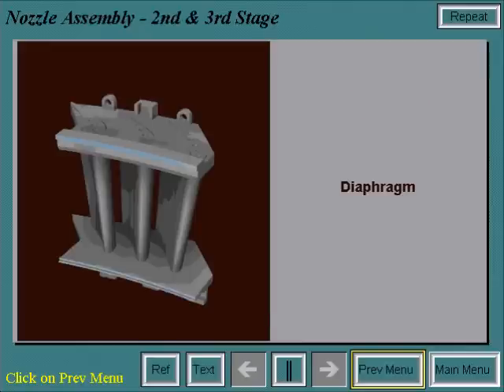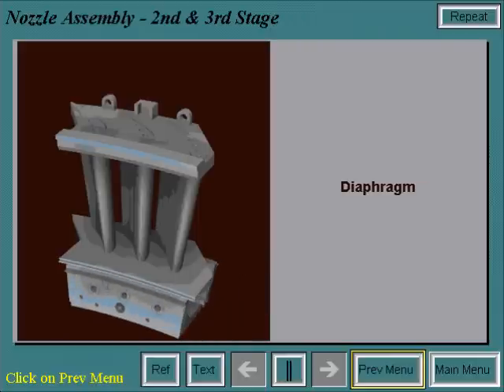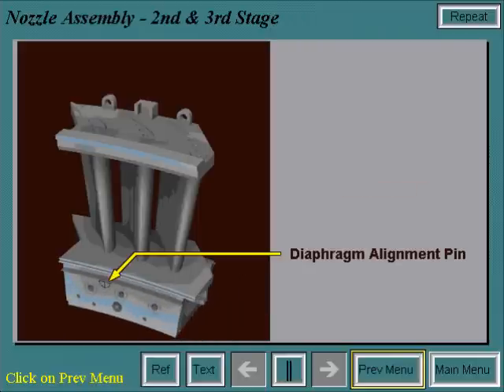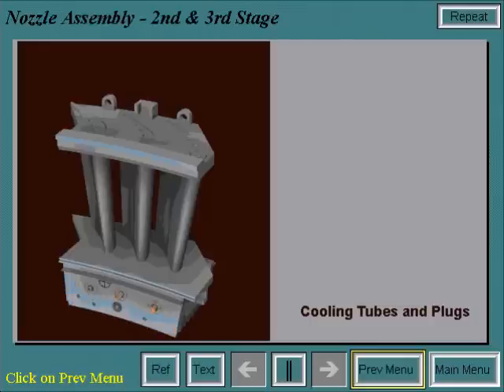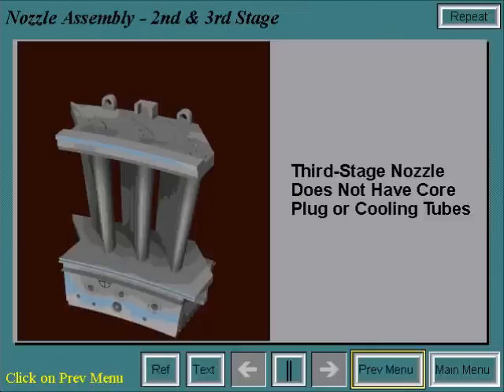The diaphragm section is then attached and a pin is installed for nozzle-to-diaphragm alignment. Wheel space cooling tubes and plugs are installed in the diaphragm. The third stage nozzle is similar to the second stage nozzle, but it is not forced air cooled, so there is no core plug and there are no cooling tubes.